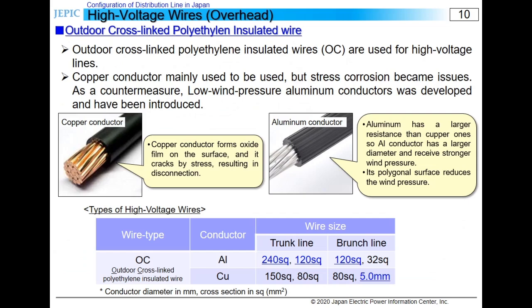Next slide is about high voltage wires. In Japan, it is stipulated by law that high voltage wires should be insulated, and the most commonly used insulation for a high voltage conductor is outdoor cross-linked polyethylene. Copper or aluminum are commonly used as a conductor, but in the past, lots of disconnections of copper wires happened due to stress corrosion. So, as a countermeasure against this, low wind pressure aluminum wire was developed and has been introduced.